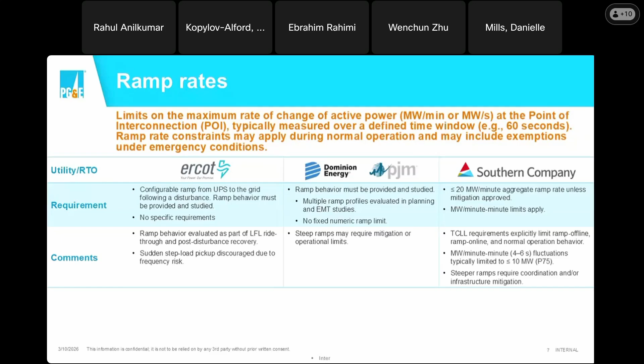Now, the purpose again of any ramp rate limit is more operational stability, limiting the burden on the AGC and the governor response. And so we know that large electronic loads can change their consumption much faster than a thermal unit's ramp capability. So that can potentially induce area control error excursions if they're not really bounded, right? And that's where the 0.036 hertz limit came into our discussion a little bit earlier as well. If we can move to the next slide, please.